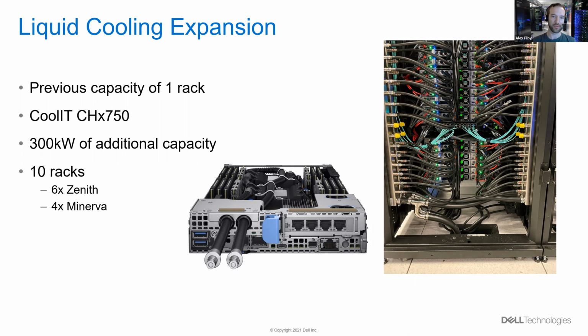Previously in the lab, we had a single rack for our high-end Cascade Lake systems. This became a challenge because the systems we were interested in for Ice Lake and Milan required a lot more power, and we didn't have the capacity to cool those with air in our lab as is. So we upgraded to the CoolIT CHX 750, a much larger unit that can hook up to multiple racks. For our install, that has about 300 kilowatts of additional cooling capacity for processors, split across 10 different racks - 6 for Zenith and 4 for Minerva.